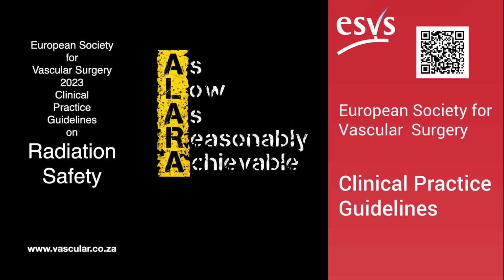Potentially, yes. So if you're using tight collimation, avoid keeping the C-arm parked in the exact same position for a very long time to prevent building up a very high PSD in one spot. Modern systems often have virtual collimators displayed on the screen to help you position them accurately without extra fluoro. Good point. What about the anti-scatter grid?